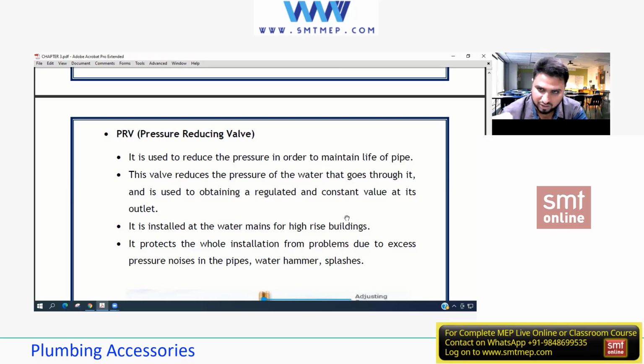It's a kind of plunger, a kind of spring over there, which comes and balances and tries to break the velocity or the gravity pressure. Then again, it starts from zero. So we need to measure where I'm getting 60 and 80 psi as per the standard. There are different standards with different values, but mostly it is 80 and 60, because the most used are IPC and UPC. So we need to check this and install one PRV in the riser.